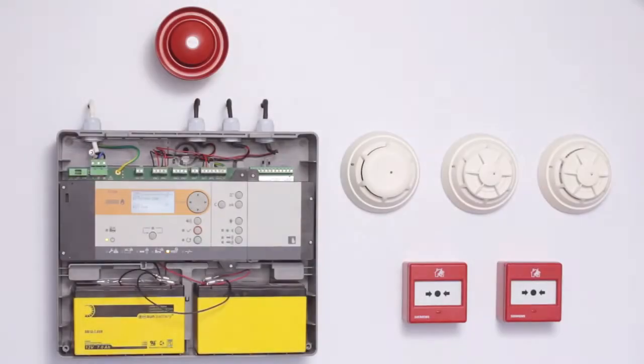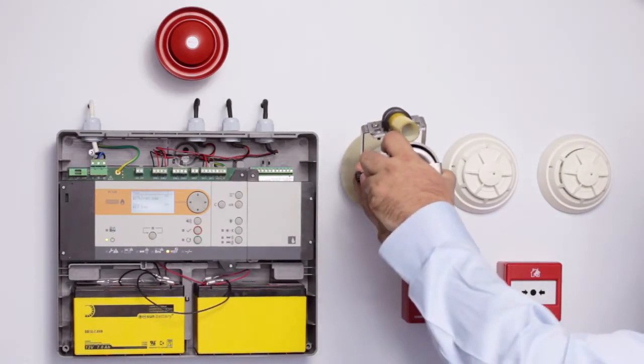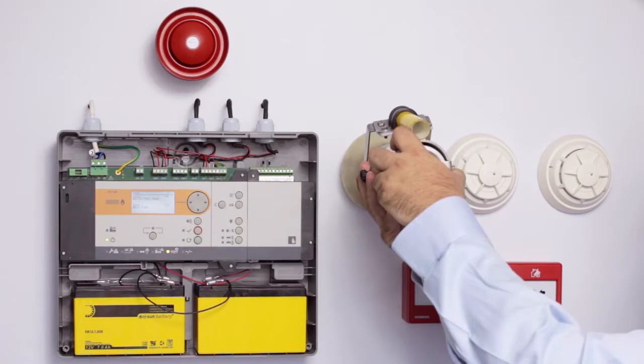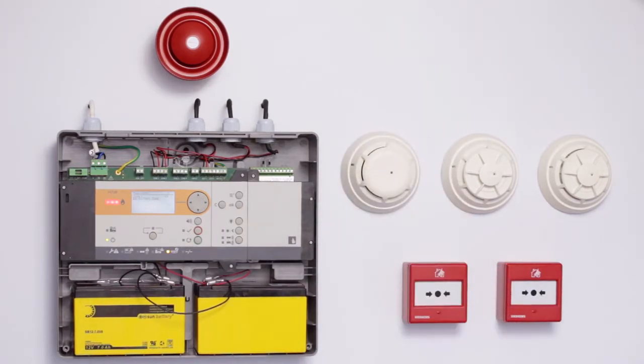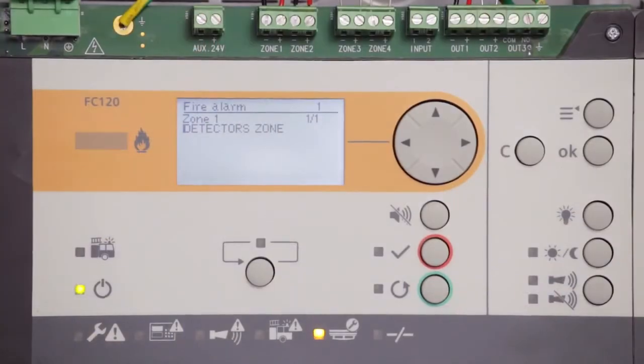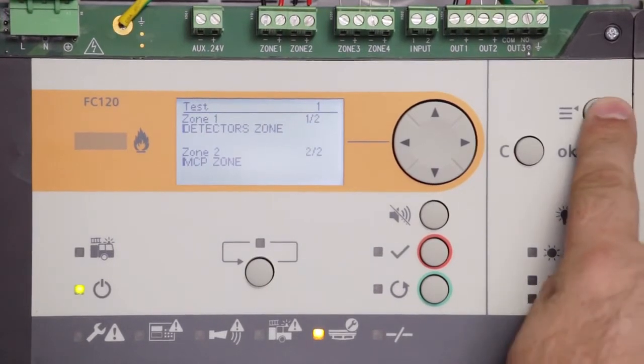How to test a smoke detector. Enable test mode for the zone. Place detector tester RE6 or RE8ST on detector head. Wait until the LED is on. The sounder sounds for 1 second. Remove the testing unit. The test alarm automatically resets after 15 seconds. Set zone to normal mode operation.